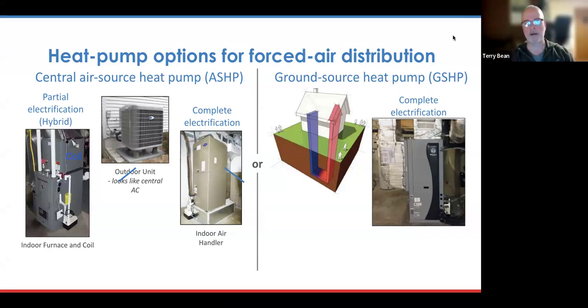So to the right, we have ground source heat pumps. These can use forced hot air distribution, but they can also use hydronic distribution as well, potentially. One advantage of a ground source system, and we noticed in the chart earlier that we were looking at in terms of the operating costs, is that the ground source systems came out on top. The reason for that is that they are working with fairly consistent temperatures under the ground, right? It's a few feet below the surface of the earth. It's always about 50 degrees, a little cooler than that in the springtime, a little warmer than that at the beginning of the fall. But in general, they're always working with about 50 degrees, versus air source systems that have to work with more variable temperatures and in some cases significantly colder temperatures that have a lower heat density.